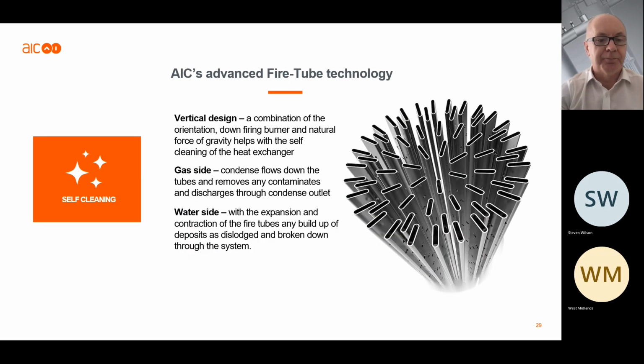Okay, self-cleaning. So you can see for all the reasons I said earlier, you've got the fire tubes there, so you've got the flue gases going down inside the tubes. You've got it condensing, so it's turning to liquid and washing out any gas residue. And on the water side, again, as I said, any build-up of contaminants on the side of the fire tubes, then these tubes expand, contract, and it'll shake off the debris and break it out and go through the system.